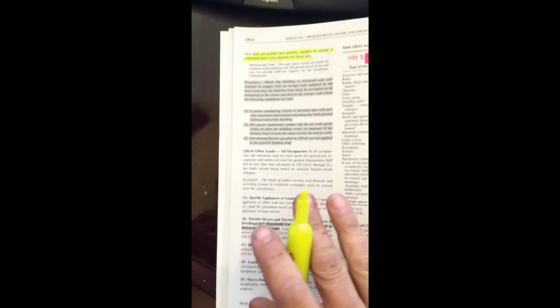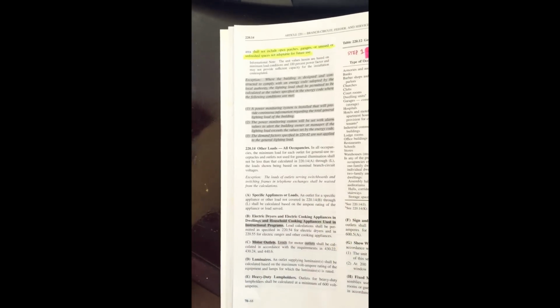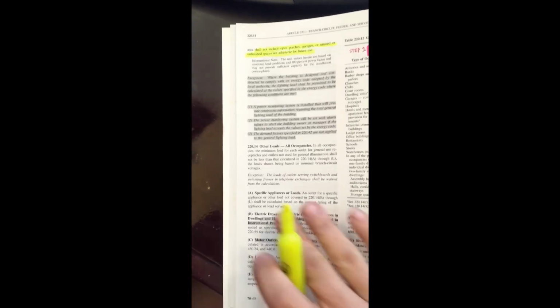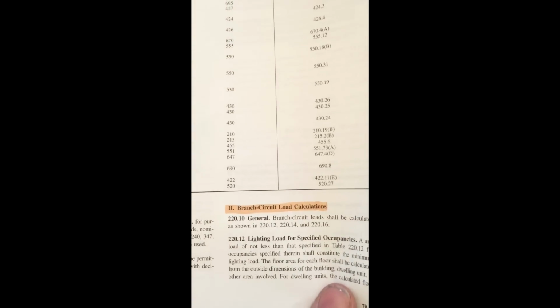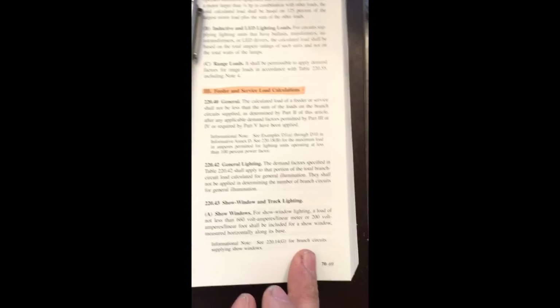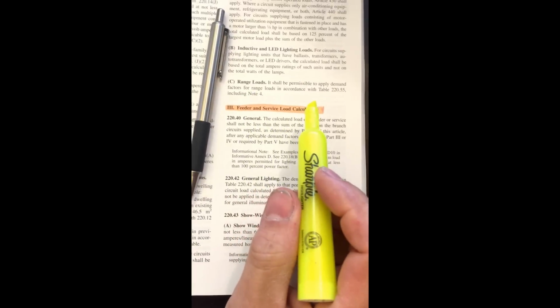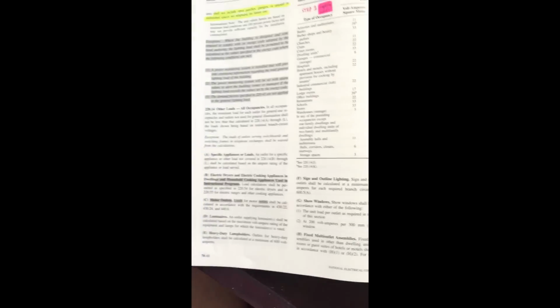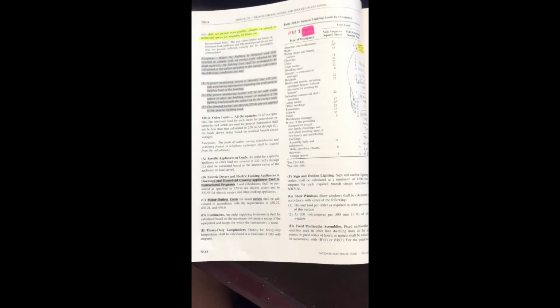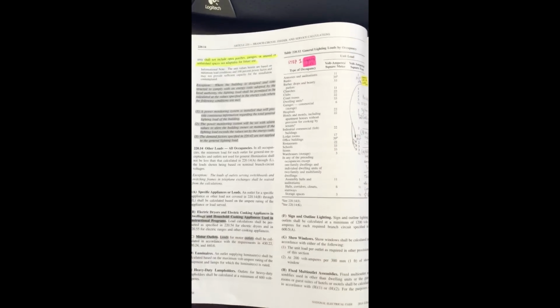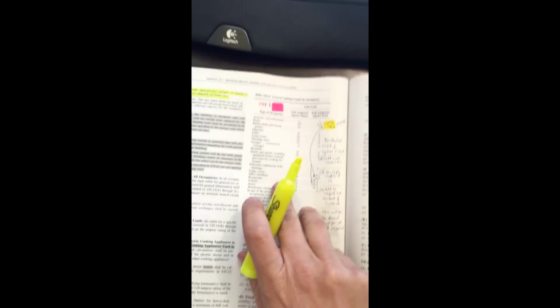Everything that I'm going to cover here in the next few minutes is all going to be considered the standard method of calculation. Part 2 here, which is considered to be the branch circuit load calculations, and Part 3, which starts on page 69, where it says feeder and service load calculations, both of these parts are considered to be the standard method of calculation. Okay, now step 1, when we're doing service calculations, the first thing we need is we need to calculate the lights.